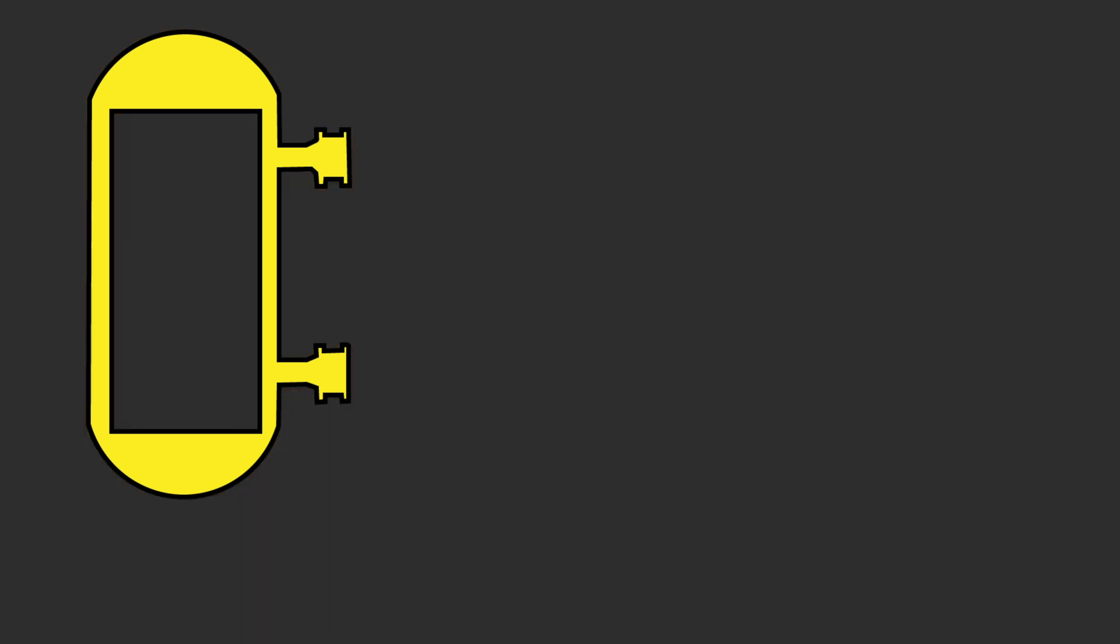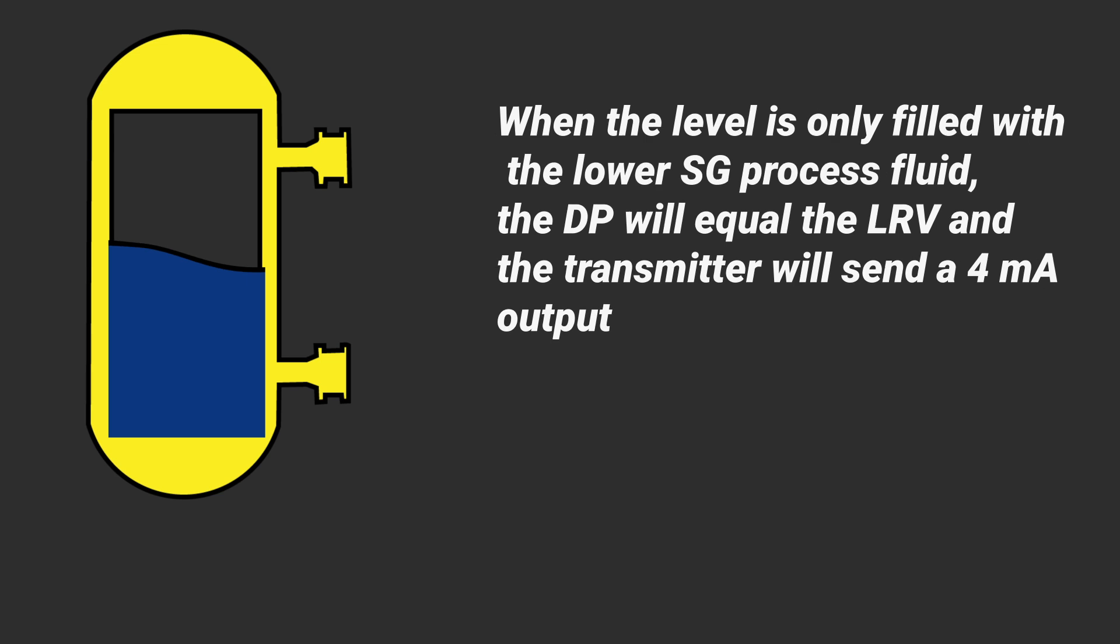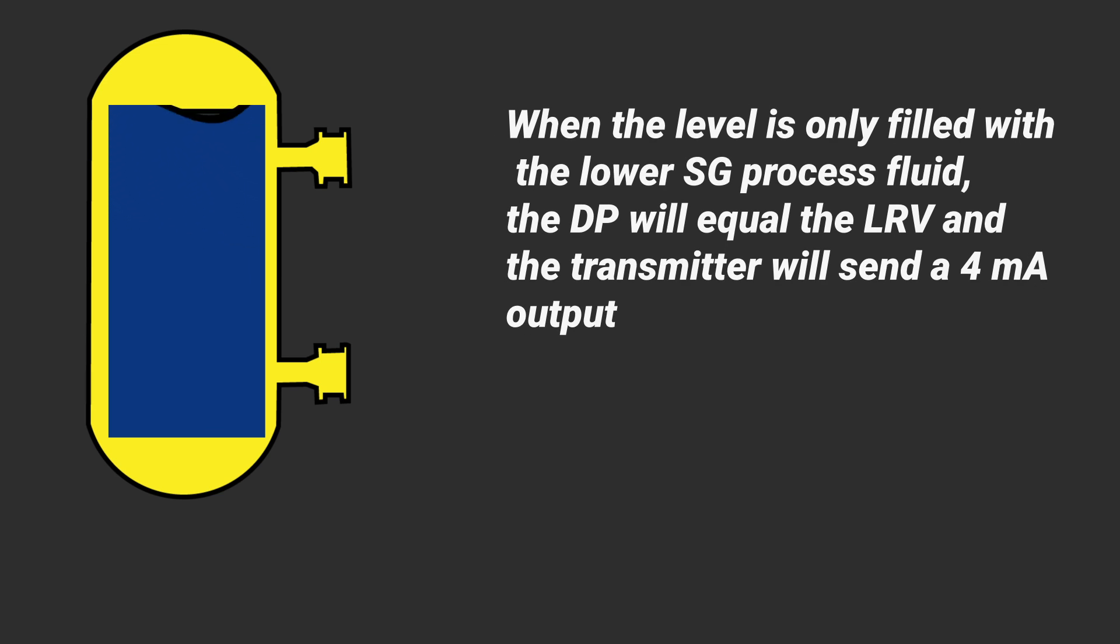Rule number two, when the level is only filled with the lower specific gravity process fluid, the differential pressure will equal the LRV and the transmitter will send a 4 milliamp output.